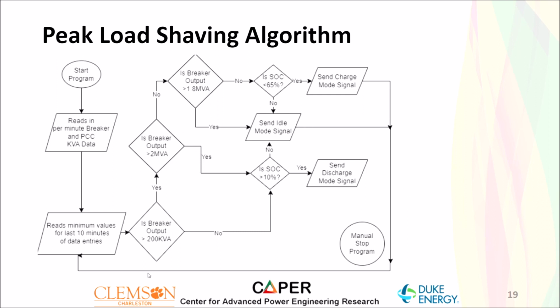So if it's not in an outage scenario, we want to see if the breaker output is greater than 2 MVA. And if it is, then we'll do something similar to the outage scenario where we check if the state of charge is greater than 10%, and if it is, we'll discharge the battery, and if it's not, we'll send it to idle mode. If it's not greater than 2 MVA, we then see if it's in between 1.8 MVA and 2 MVA, which is kind of the gray zone where we don't really want the battery controls to do anything, because we don't want to waste energy and we don't want to overcharge for no reason. So if it is greater than 1.8 MVA, then we know that it's in between these two, and we just keep it in idle mode until the next data set is read.